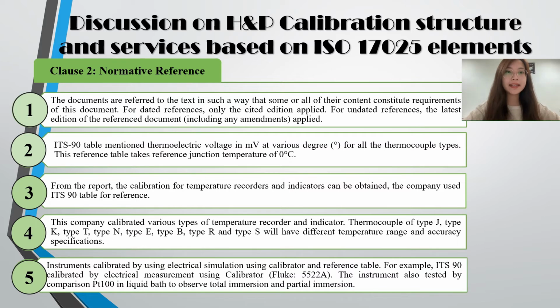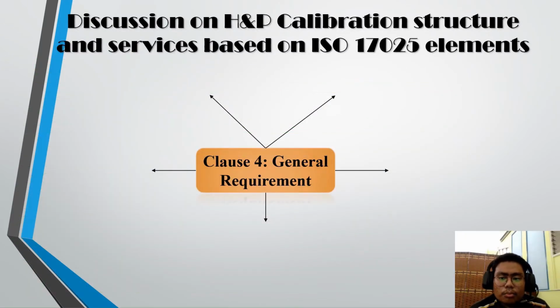For example, ITS90 is calibrated by electrical measurement using a calibrator such as Fluke 5522A. This instrument is also tested by comparison with PT100 in a liquid bath to observe total immersion and partial immersion. Today, I'll present my part, which is clause 4, general requirement.